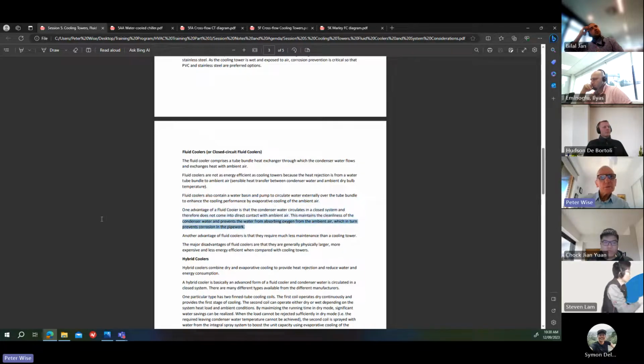One advantage of a fluid cooler is that condenser water circulates in a closed system and doesn't come in contact with ambient air. This maintains the cleanliness of the condenser water and prevents the water from absorbing oxygen from the ambient air, which in turn prevents corrosion in the pipework. And you don't get the same buildup of sludge and scale because you're not absorbing the dirt from the air into the water.